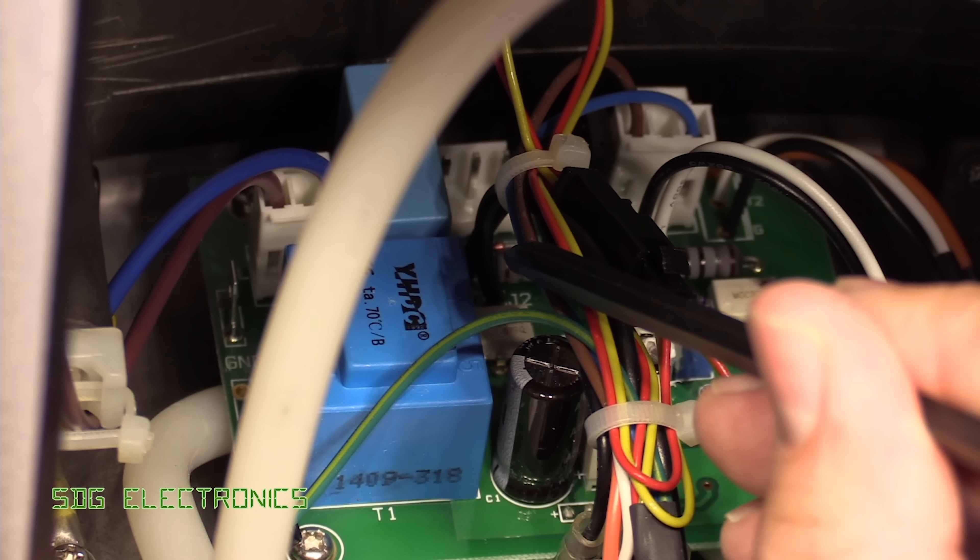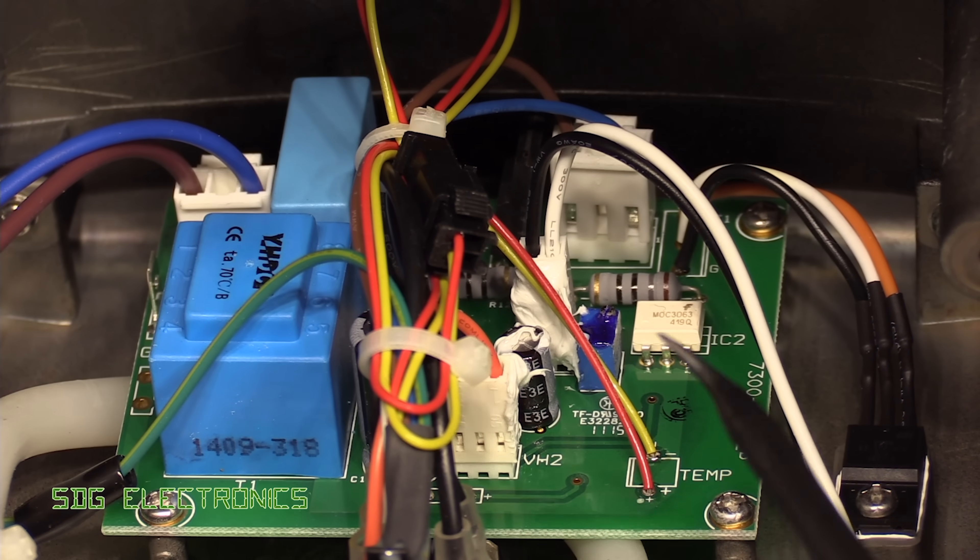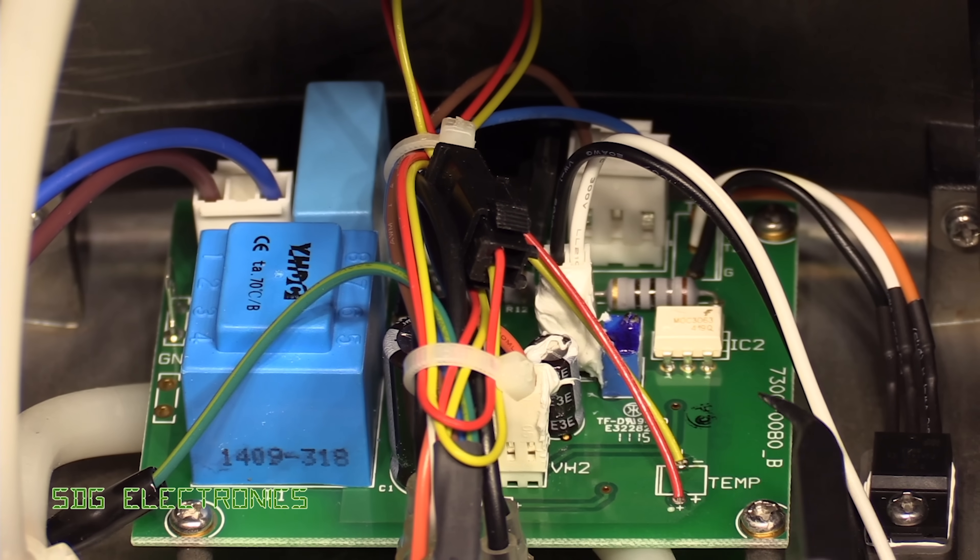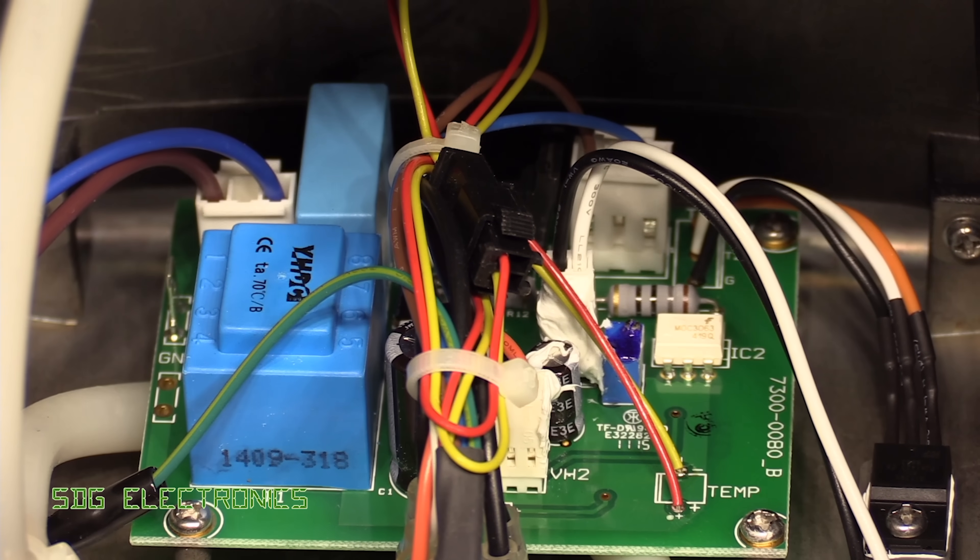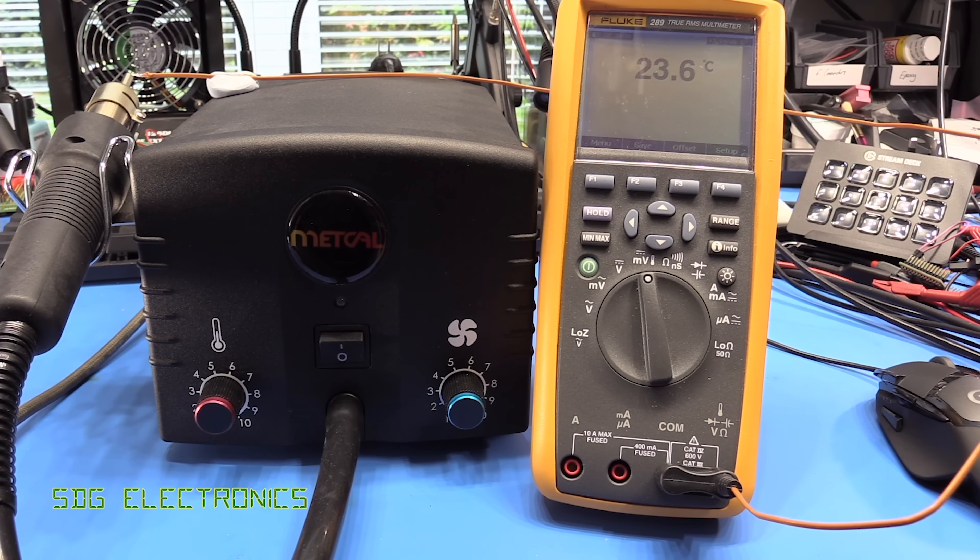Yeah, not a huge amount to go wrong. Quite a simple design. And this is what I mean, although there are some electrolytic capacitors on here, there's really not a huge amount to go wrong. The only thing that you're probably ever going to need to replace on this thing is the heater in the handpiece.